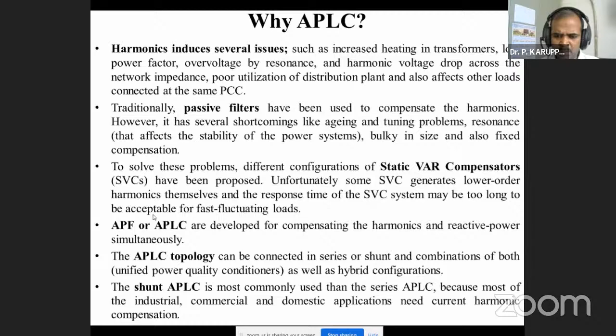That's why active power filters, or active power line conditioners, were developed for compensating the harmonics as well as the reactive power simultaneously. The APLC topology can be connected in series or in shunt, or a combination of both, as well as a hybrid configuration. However, the shunt active power filter is the most commonly used compared to the series, because most industrial, commercial, and domestic applications need current harmonic compensation because of the loads we use in our home appliances. Now, how do we design the shunt active power filter? This is the question.